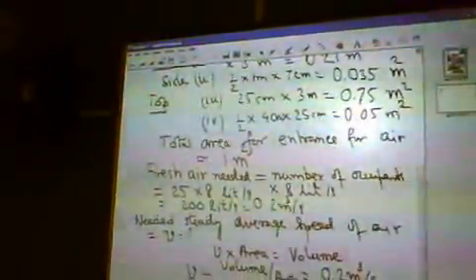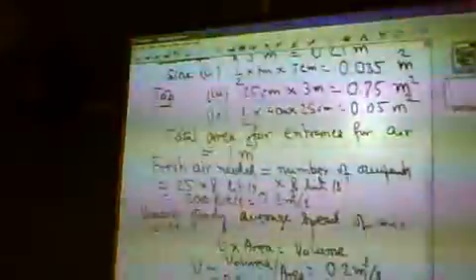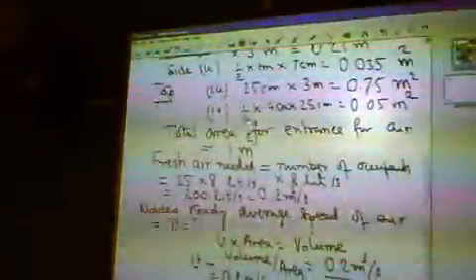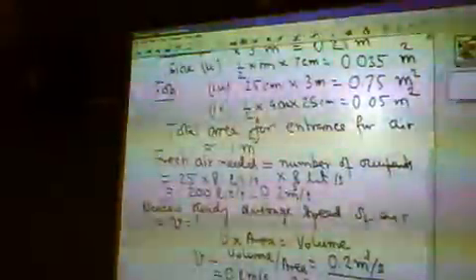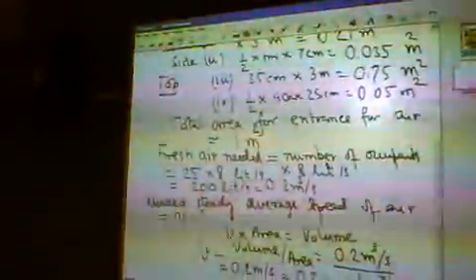Fresh air needed can be calculated using the formula: number of occupants multiplied by 8 liters per second per occupant. If I have 25 students, that will need 200 liters per second of fresh air, that is 0.2 cubic meters per second.